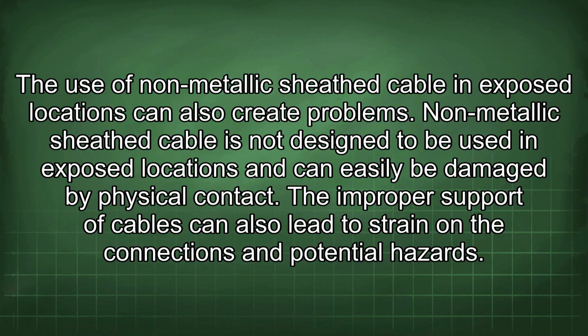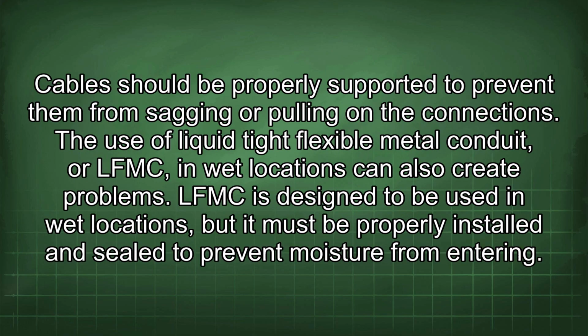The improper support of cables can also lead to strain on the connections and potential hazards. Cables should be properly supported to prevent them from sagging or pulling on the connections. The use of liquid-tight flexible metal conduit, or LFMC, in wet locations can also create problems.